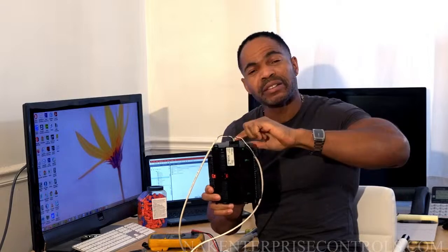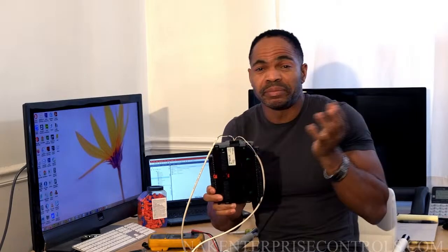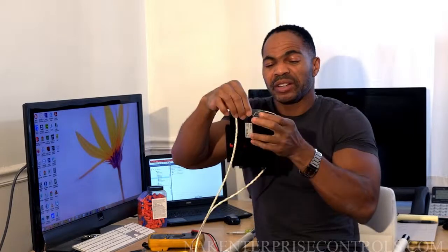It's close enough to this device, so they figure, well, they'll just tap in and connect that device and put it on the trunk. And they're done. Is that a daisy chain connection? Or if that's done, does your network remain a daisy chain? No. Now it becomes a star connection.